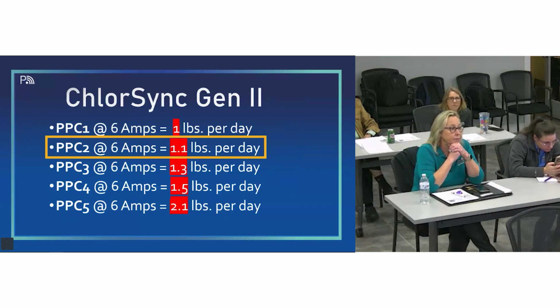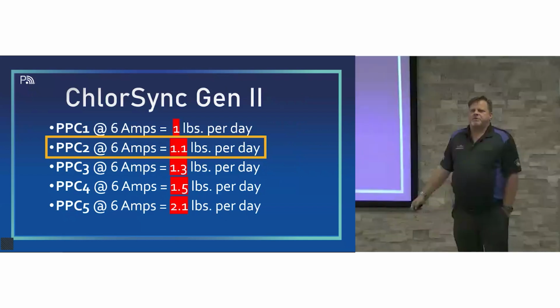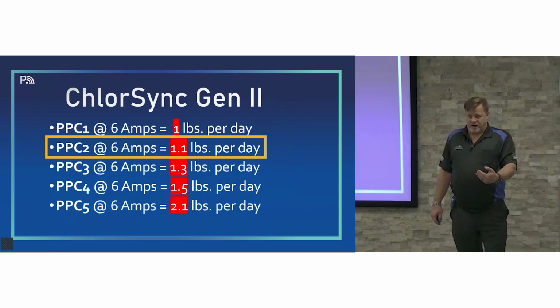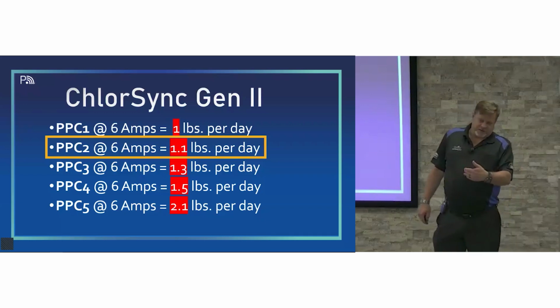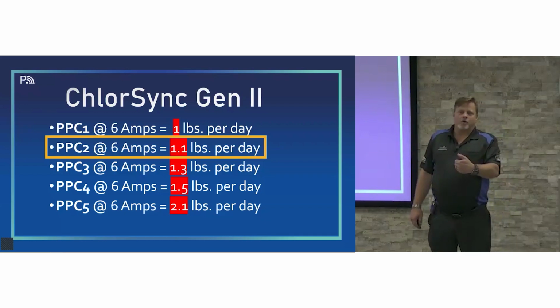Would that be the boost cycle? That's the same as a boost cycle, yes. So if you press boost, it automatically defaults to 100% for 24 hours of runtime? 24 hours of runtime, yes sir. So the pump has to be running for 24 hours. If the system experiences a no-flow message, like the pump shuts off, the countdown stops, and it won't pick back up until flow is reestablished.